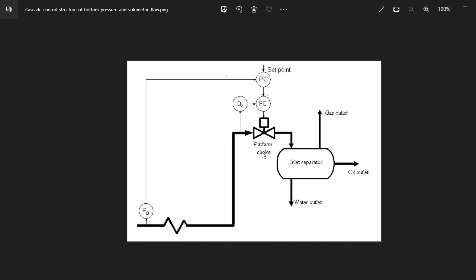We have a pressure transmitter which feeds a pressure controller, and if I apply a set point there, the pressure controller output becomes the set point of the flow controller. The flow controller already has an input from the flow transmitter, and then the output of the flow controller actually goes to the valve. So this is how a cascade system works. For this example, the pressure controller — the PC — is the master controller, and the FC here is the slave controller.